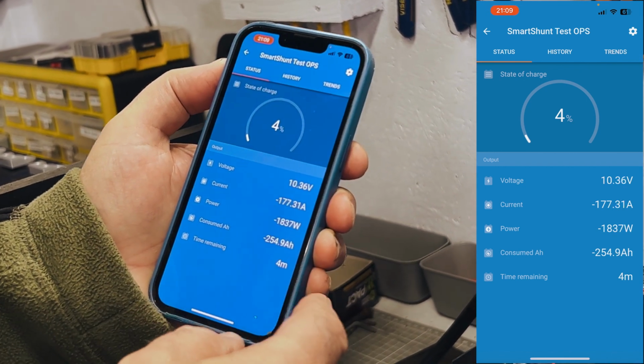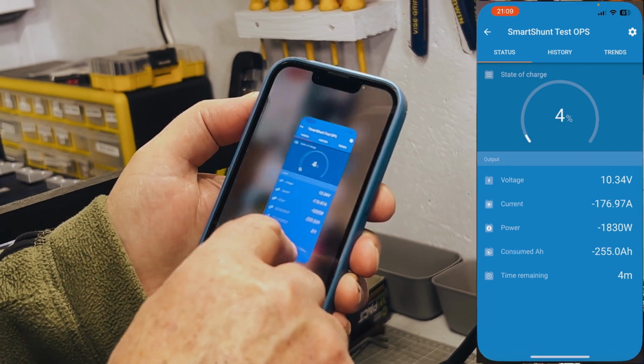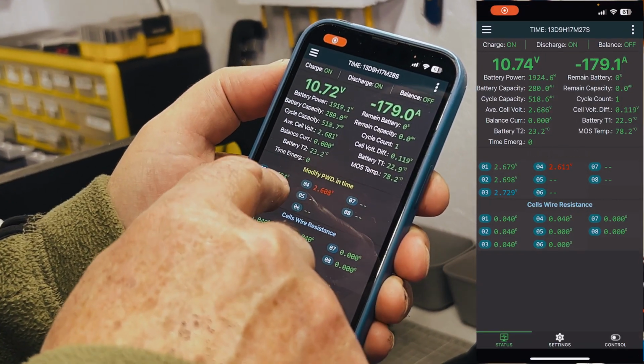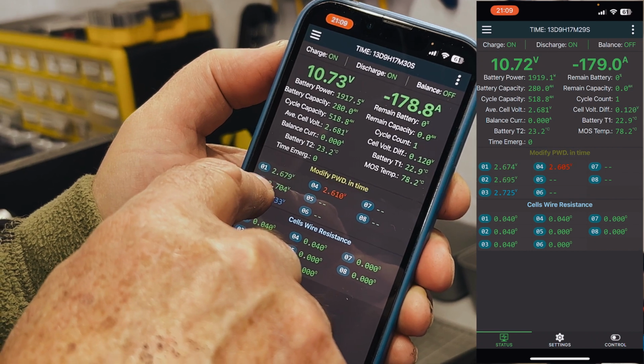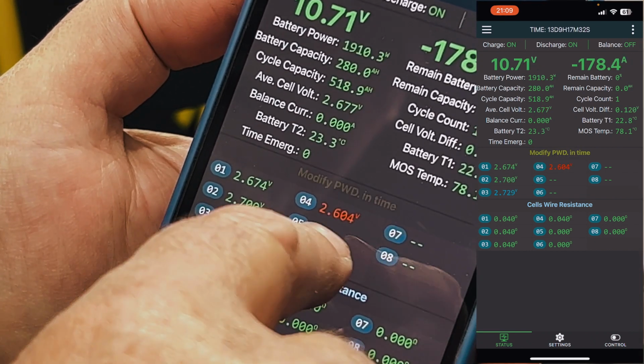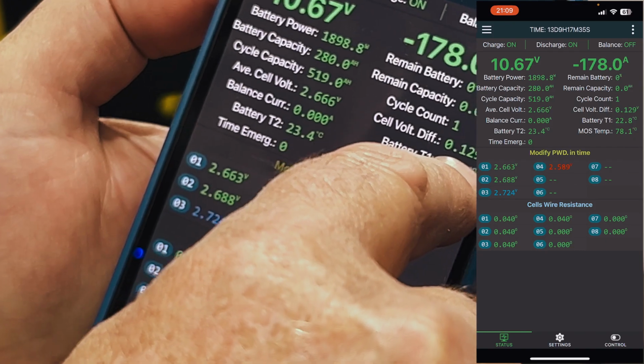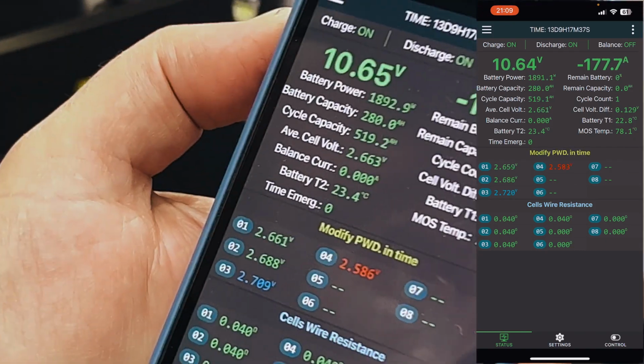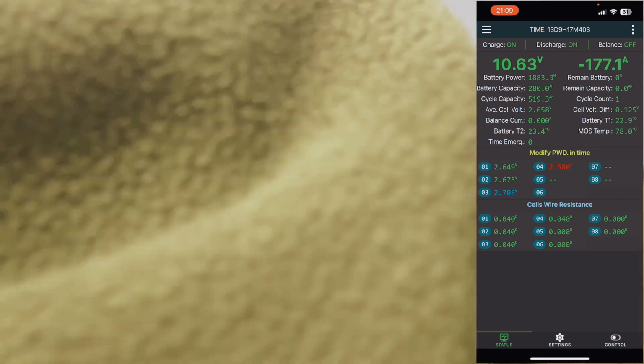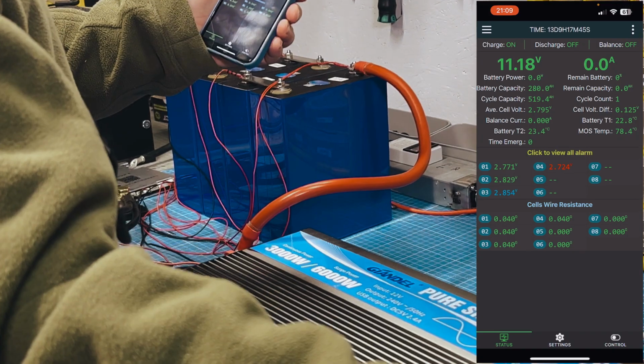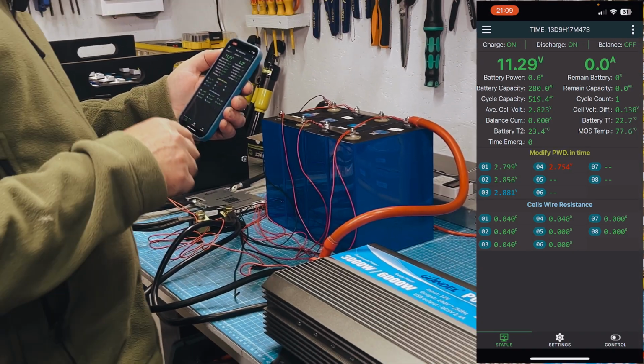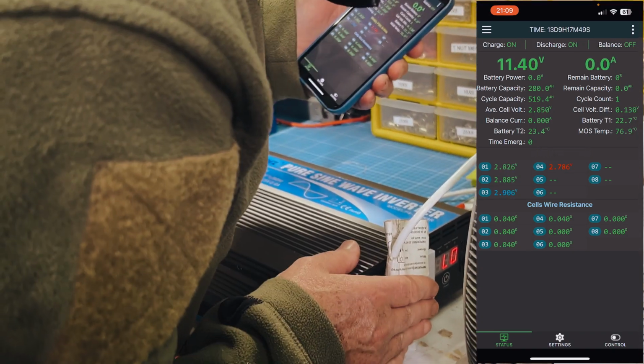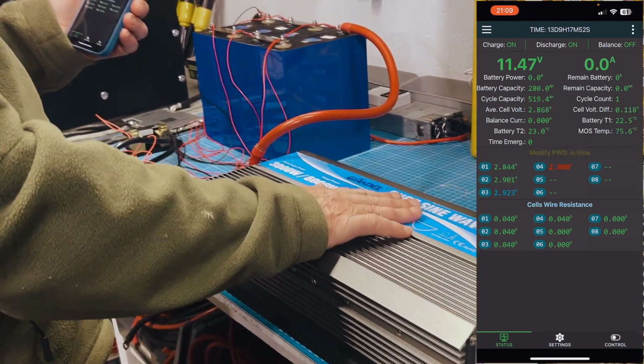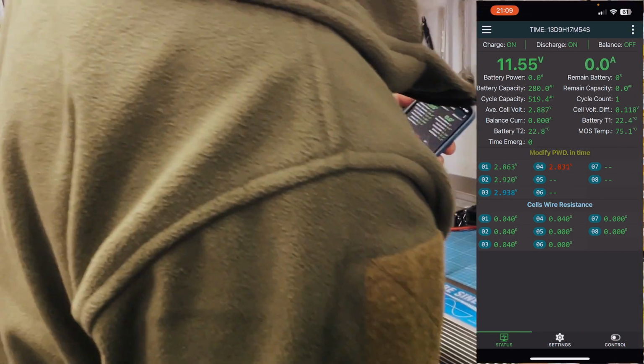Supposedly we have 4 minutes to go. Let's see what the cell voltages are again. So we're dropping down quite rapidly. As you can see, we're at 2.6 something, and the diff has gone to 0.12, which is to be expected. So I'm going to turn this back one. In fact, it has just - I was just too late. I think actually the inverter has turned off because the voltage got too low. So let's turn this right off.